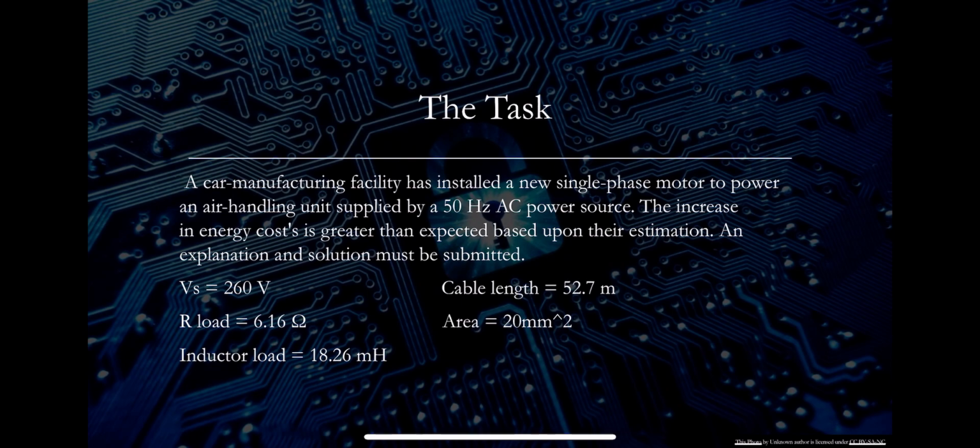The voltage source was 260 volts, the load resistance was 6.16 ohms, the inductor load was 18.26 millihenries, the cable length was 52.7 meters, and the area was 20 millimeters squared.